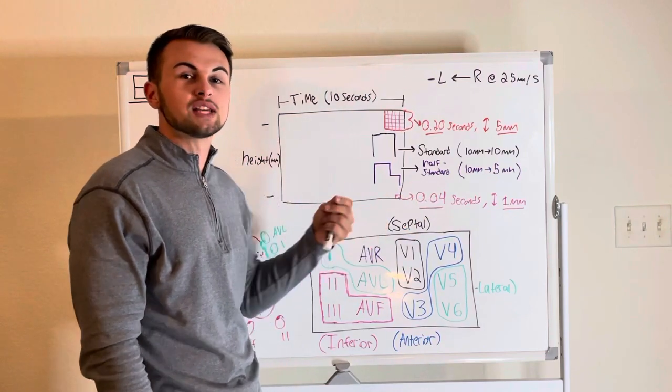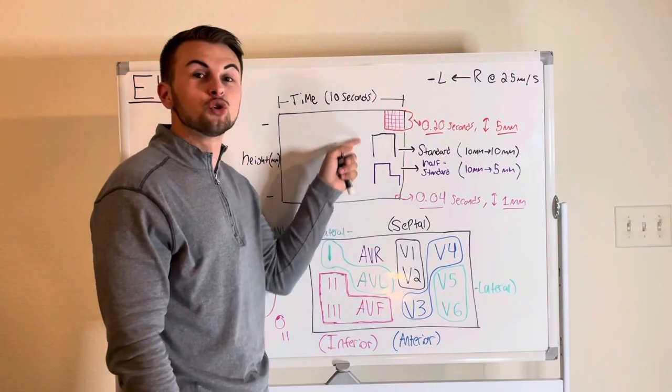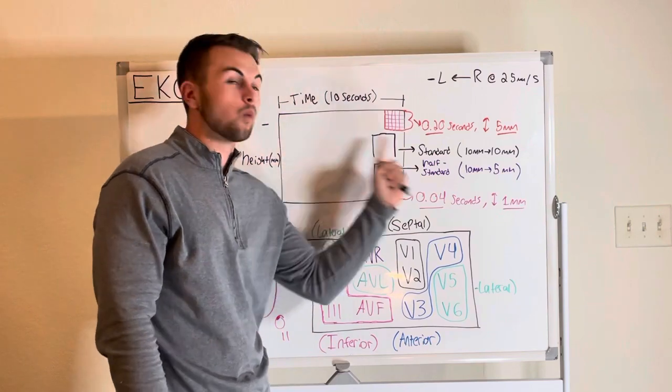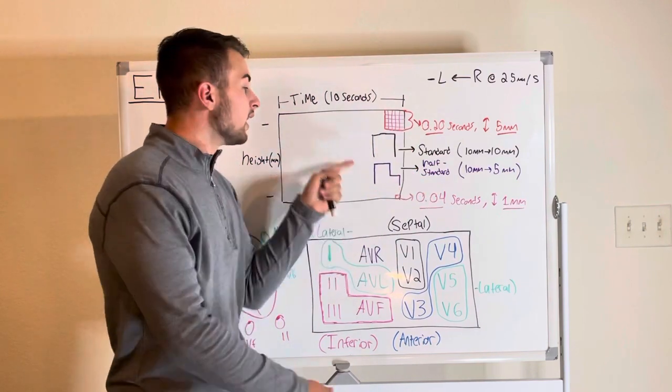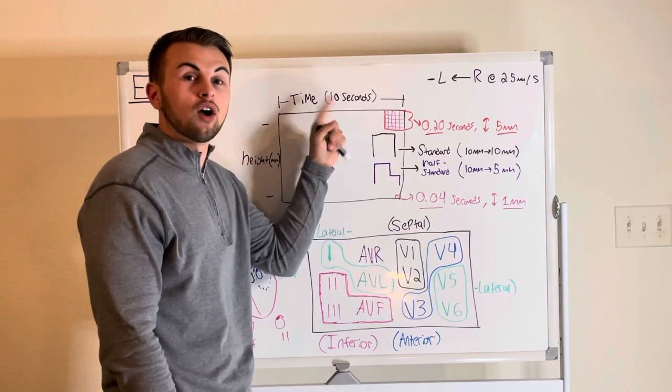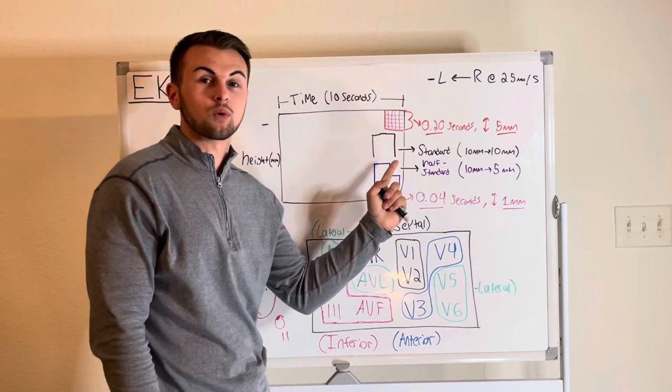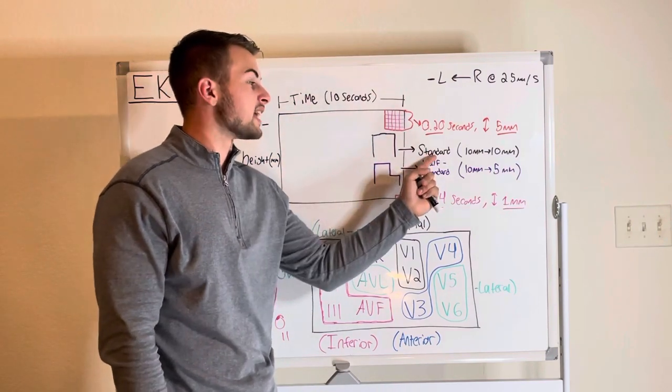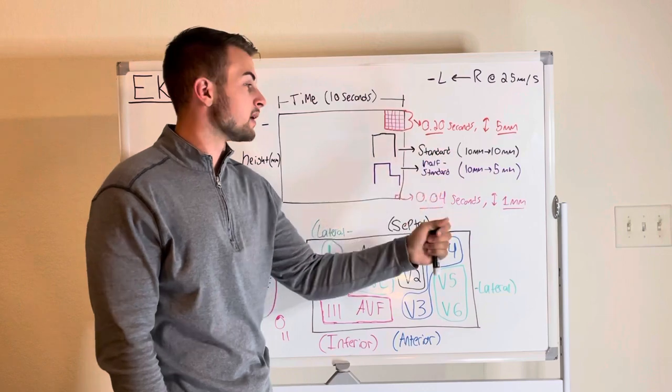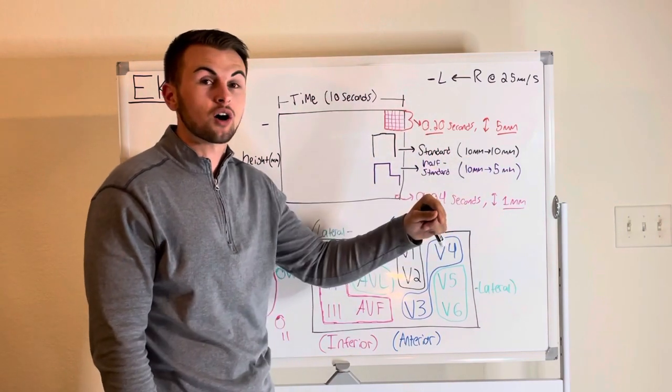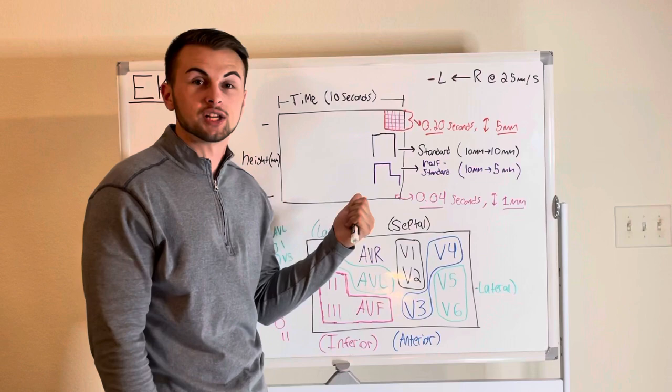This means that you will see a box that is two big boxes tall and one big box wide or 10 millimeters tall and 0.2 seconds wide. This is called standard calibration. This means if a box is 10 millimeters tall it is going to be 10 millimeters tall on the sheet.